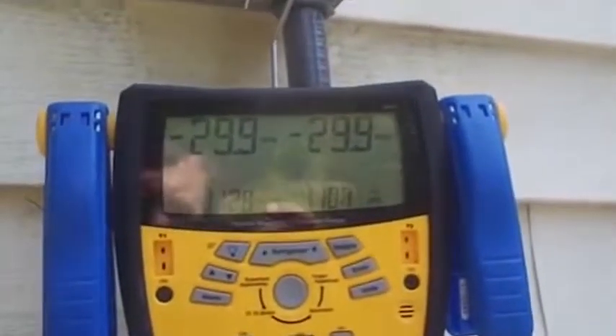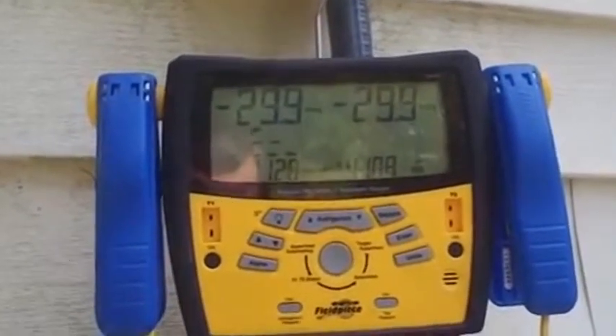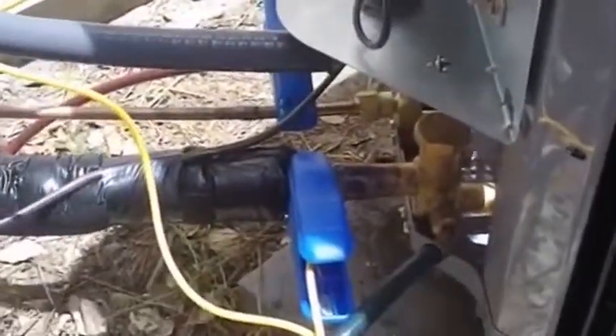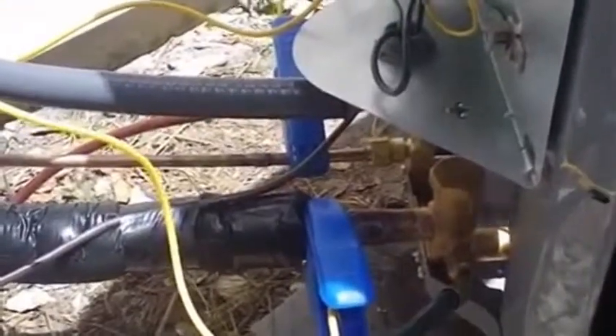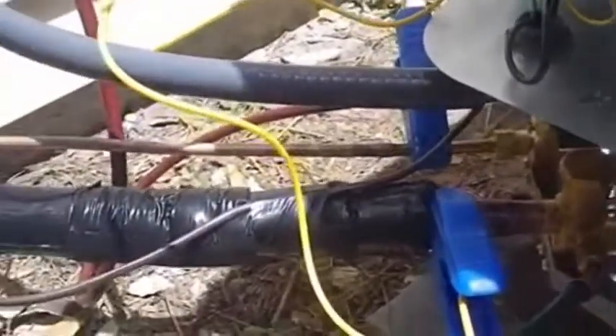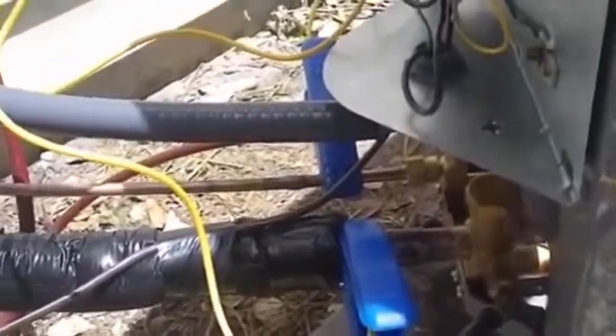Alright, a few minutes later we're at 1130 microns, which is not optimal. So we have to think our way around this. Why are we not going down as quickly as I would like? Okay, what I had to do with the vacuum was put it through a triple evacuation again. Pump it full of nitrogen, bring it back up to atmospheric pressure, evacuate.